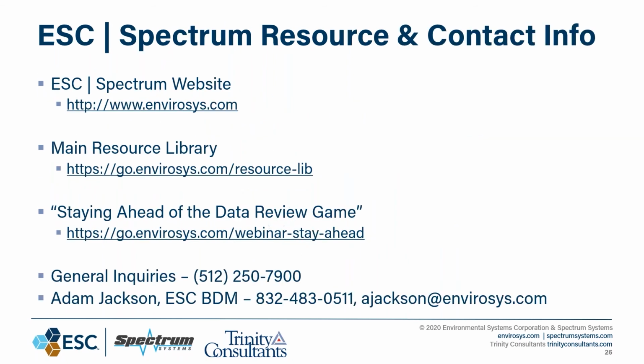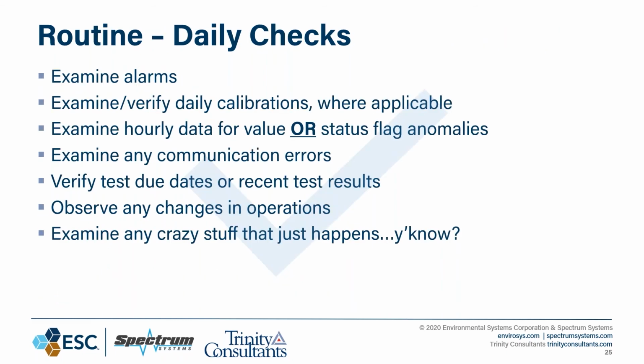We're discussing DAS here, but your DAS for anything bad that can happen could be programmed in with certain alarms. Some of those alarms for these routine daily checks are things like someone left the door open on the CEMS shack, and you get an air conditioning alarm. Simple stuff like that can create calibration failure, can create exceedances, and your DAS should be telling you the health of the overall mechanical condition, as well as you personally going into that CEMS shack daily.